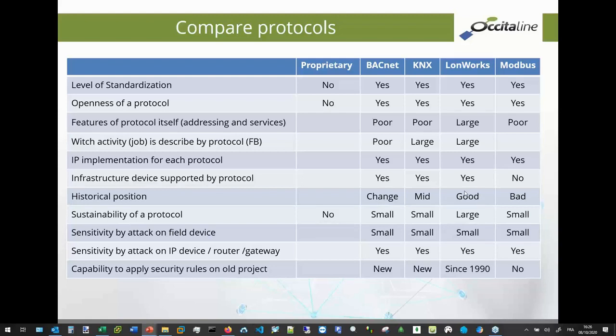Infrastructure devices: I have not explained every layer, repeater, router, and switch. The most important is the router. The router exists in BACnet, in KNX, and in LON. Not in Modbus, because it's just a router between LON, IP, Modbus, and MSTP, but it's not exactly a router in this case.